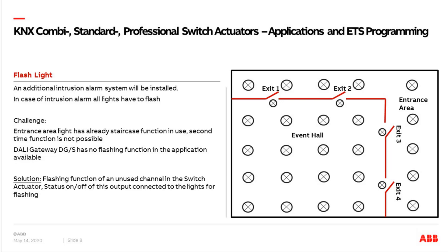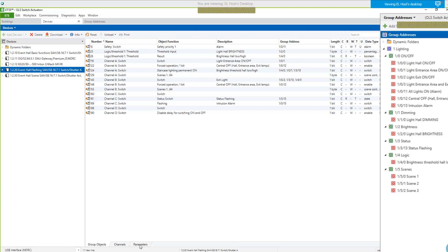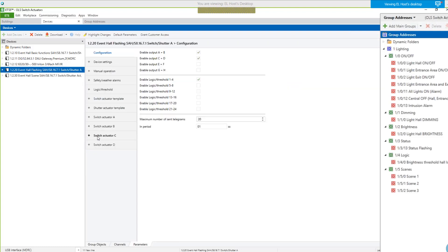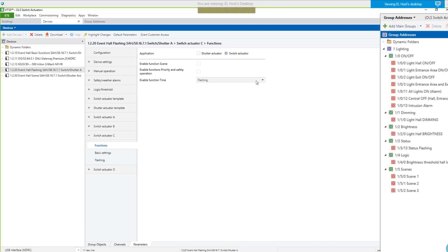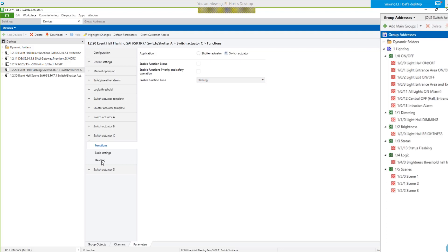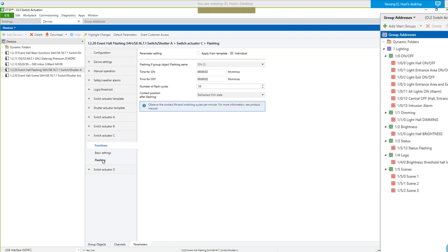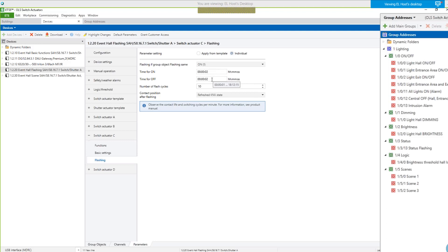Let's have a look at the ETS parameters. I use channel C here — that's the reason why I enabled channel C and D as a second block. Going to switch actuator channel C — flashing. First, you have to enable the time function, and this is the choice between three options: staircase, delay on and off, and flashing. I use flashing here. Then an additional parameter page appears. You set an on telegram to start the flashing, and the time for on and off. You can adjust here in hours, minutes, and seconds. In my case, I use two seconds on, two seconds off — the minimum time is one second.